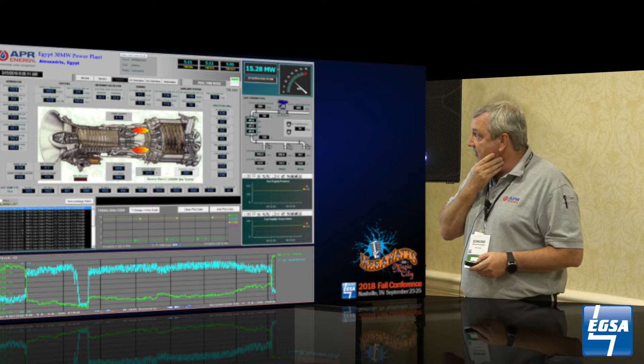Similar to the same philosophy we use for our gas turbines. This is a GE LM2500 family. Monitoring the turbine for its performance, we know when to take the turbine down to do a water wash. It's one of the terminologies you don't hear much on the diesel recip side. You'll hear about it maybe in the larger engines where they have to wash the turbos on 8, 10, 20 megawatt engines, but not so much on the smaller engines. We take the turbine down because we're getting a lot of dust. Even though we've got really good filtration systems on the front end of the turbine, we still get dust particles coming through into the compressor section in here.